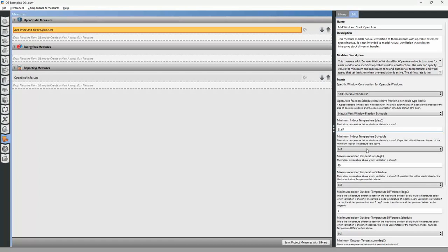You could create a custom schedule — for instance, occupants would never open windows in the mornings unless the indoor temperature was a certain value, but might open them in the afternoons at a different value. There is also a maximum indoor temperature above which ventilation is shut off — if the temperature inside gets above this value, occupants will always close the windows. You can create a custom schedule for that as well.